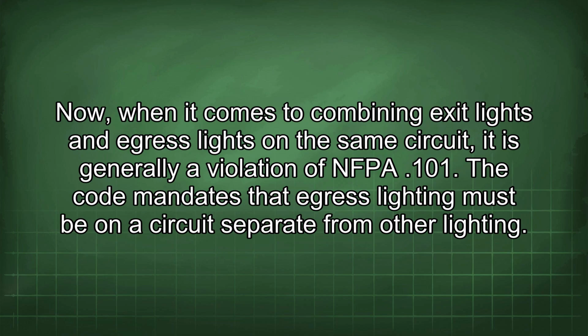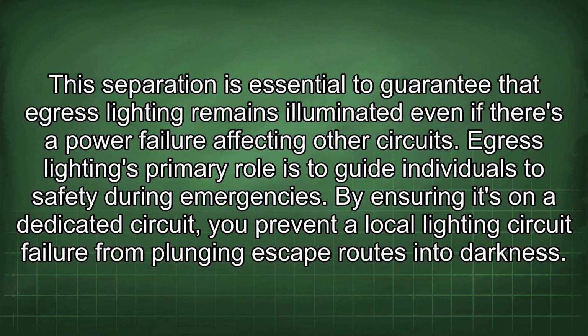Now, when it comes to combining exit lights and egress lights on the same circuit, it is generally a violation of NFPA 101. The code mandates that egress lighting must be on a circuit separate from other lighting. This separation is essential to guarantee that egress lighting remains illuminated even if there's a power failure affecting other circuits.